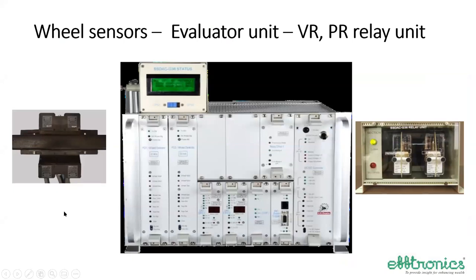This is how it looks like. You can see the 8 cards here: 1, 2, 3, 4, 5, 6, 7, and 8. All the 8 cards. The last one is the power supply and these two are the signal processing cards, the pulse detection cards. And these two are the processors. This is the event logger. One is the relay driver, like this. Now, these are the two relays provided just in the same location box. One is called the vital relay, the other is called the preparatory relay.